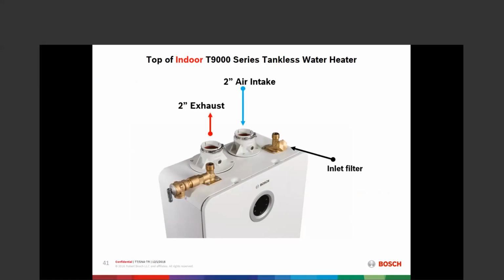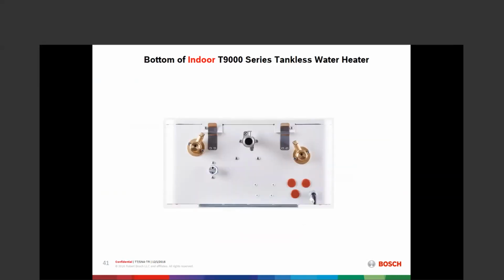On the water intake, we have an inlet filter, so it's a built-in Y strainer type configuration, a basket strainer that's going to catch debris, anything that comes off of older piping or older city water or a well situation is going to grab that debris. And then the water connection is 3/4-inch male NPT, pretty standard there, and the same thing with hot water out. Then we have the port for the included relief valve on the indoor units. The bottom looks like this. We have our flush ports, and those are garden hose thread, 3/4-inch garden hose thread. So if you're using washing machine connectors to connect to your flush pump, your pony pump, whatever it is, then very easy to connect there. Same thing on both sides.